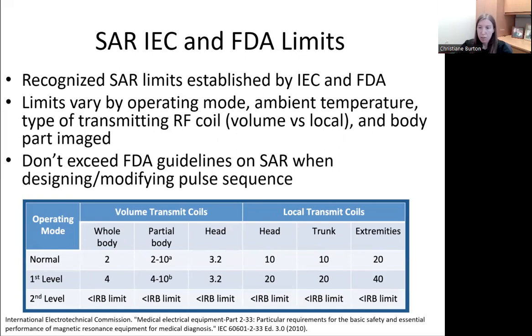The IEC and FDA jointly worked to develop the first international standards for MR equipment safety, codified as IEC 60601-2-33. This document classified SAR into various subtypes known in the table and established 3 modes of scanner operation based on the perceived risk to the subjects. These are normal mode, first level controlled mode, and second level controlled mode. Criteria for each operating mode are based principally around SAR, but also include factors such as static field strength, rates of time varying gradients, area of the body imaged, and temperature rise. The normal operating mode is the routine level at which most clinical MRI today is performed, being considered safe for all patients regardless of their condition.